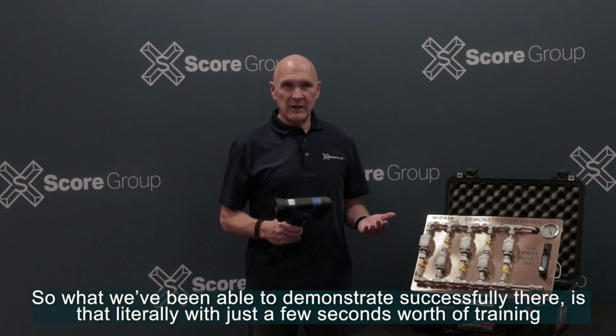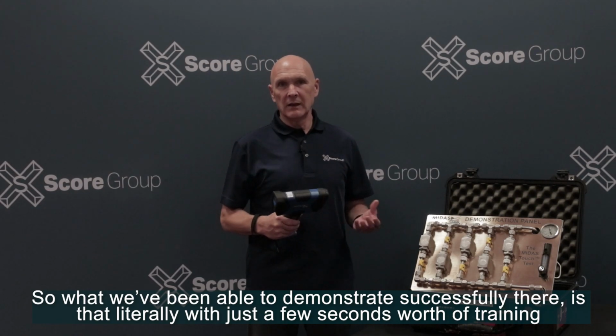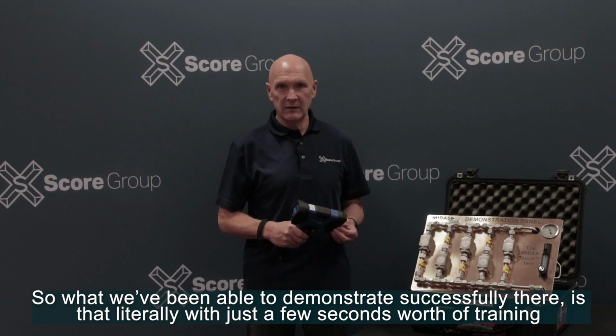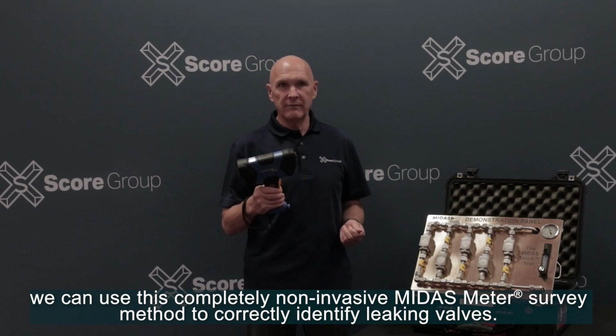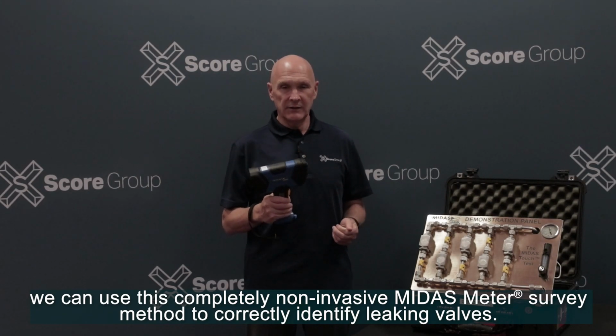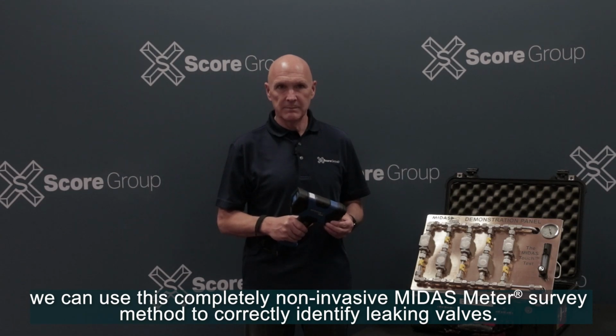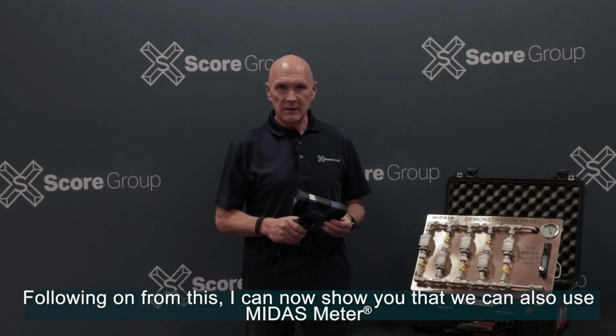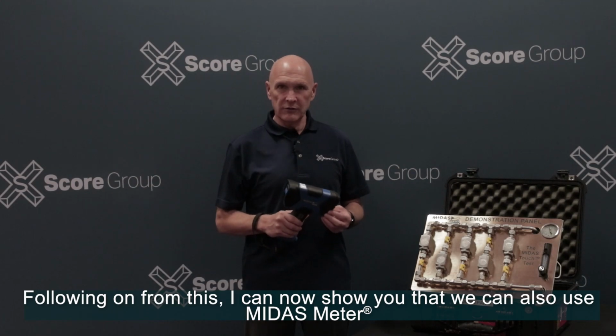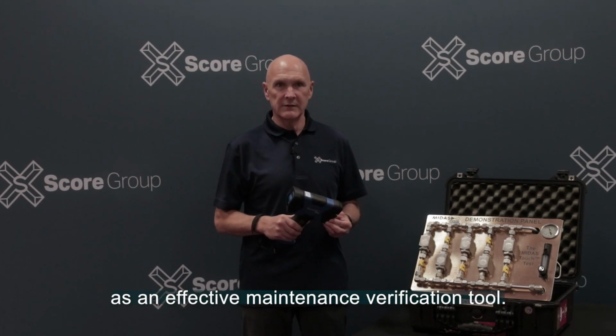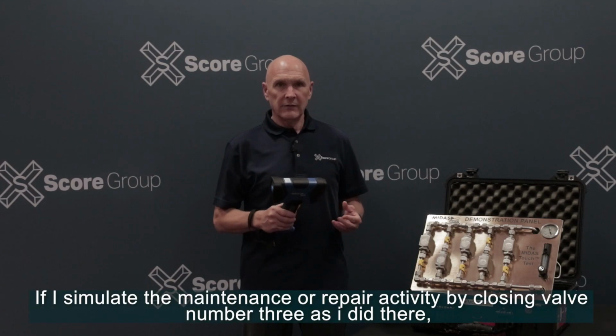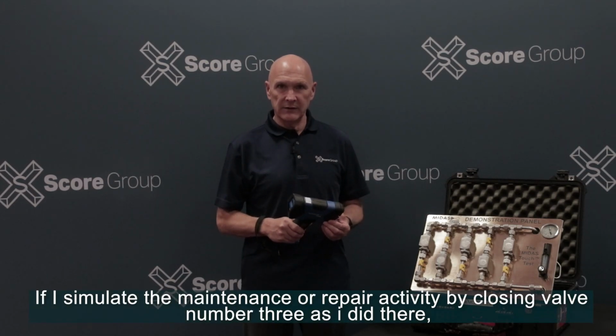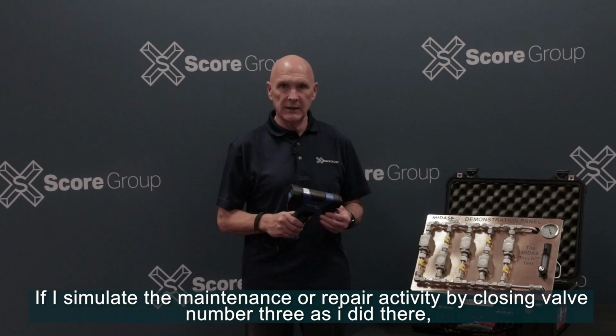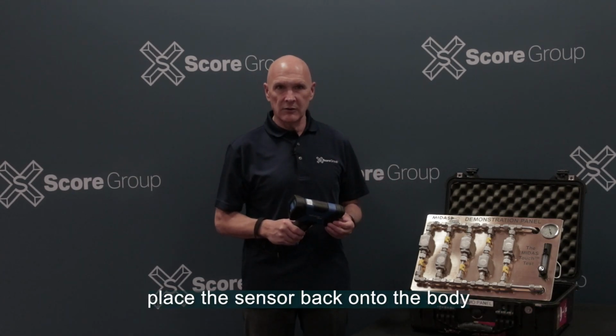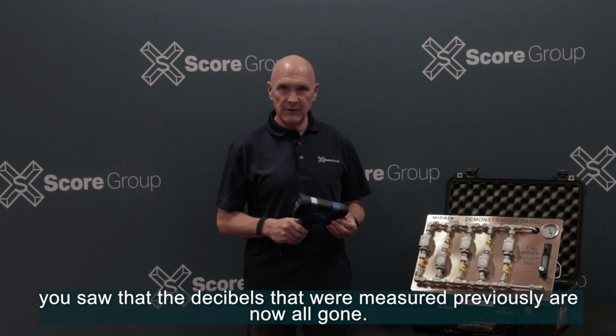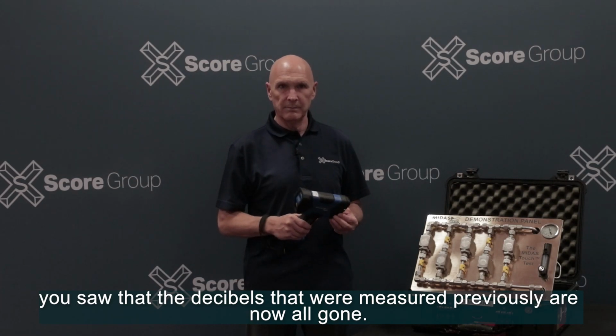So, what we've been able to demonstrate successfully there is that literally with just a few seconds worth of training, we can use this completely non-invasive MIDAS meter survey method to correctly identify leaking valves. Following on from this, I can now show you that we can also use MIDAS meter as an effective maintenance verification tool. If I simulate the maintenance or repair activity by closing valve number 3 as I did there, place the sensor back onto the body, you saw that the decibels we measured previously are now all gone.